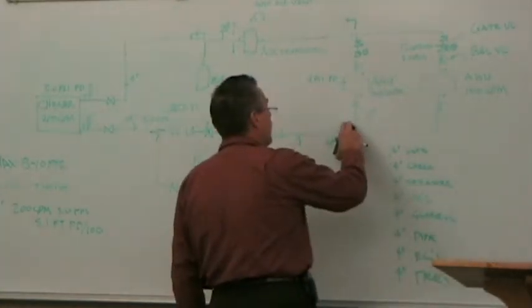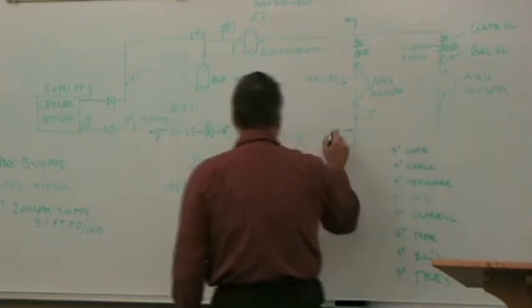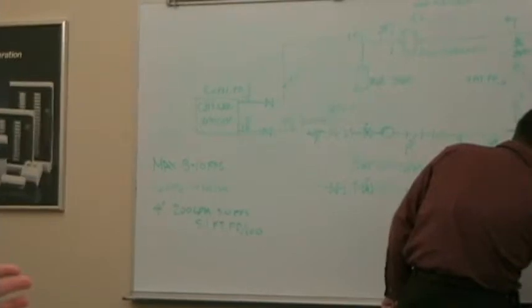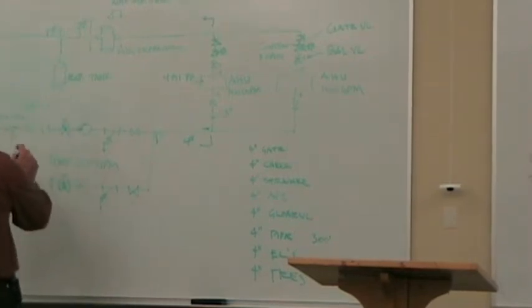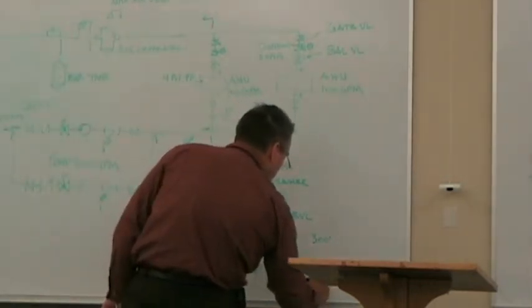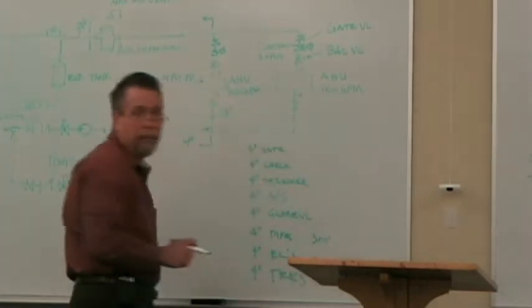But let's just say they're not. So we'll know the differences. I've got a straight through T. We're going to say that all this piping from here, here, here, is 300 feet. Okay? And I've got 2 T's. I've got, who knows how many L's, just come up with a number, let's say 20 elbows in the pipe. And I'll show you how much pressure drop each elbow is.